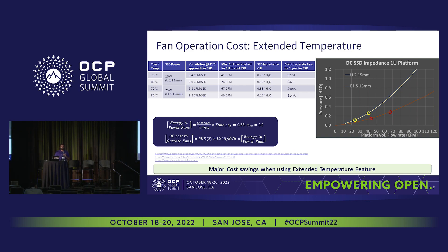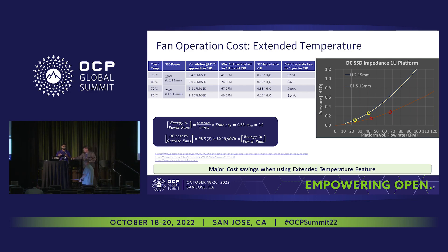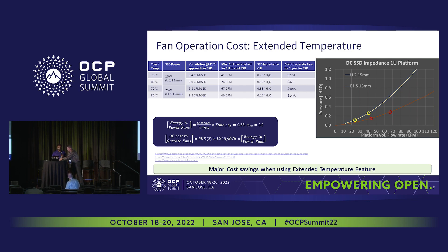The cost of operation for one new system for one year of SSD cooling: if you have a 70 C touch limit it's going to be almost $22. However, if you go to 80 C touch limit, you can reduce the cost all the way down to $4. So extended touch limit on our SSDs is not only eco-friendly, it also benefits the cost of operation that the fans have to run. It's very beneficial from all angles.